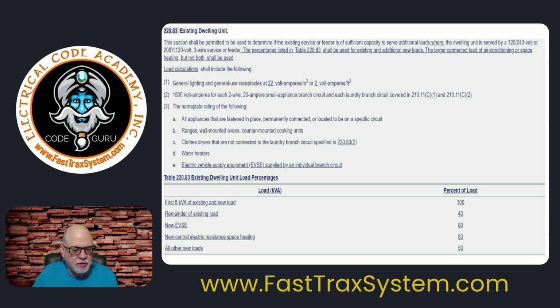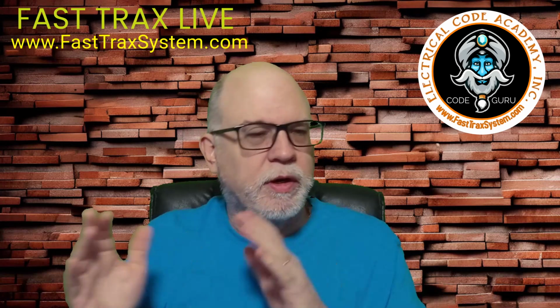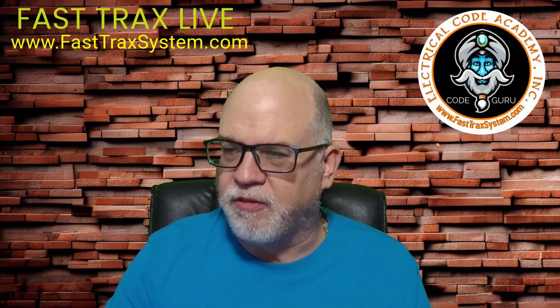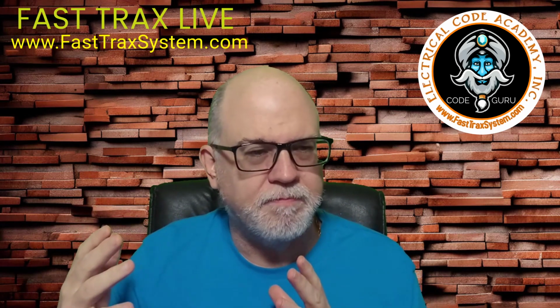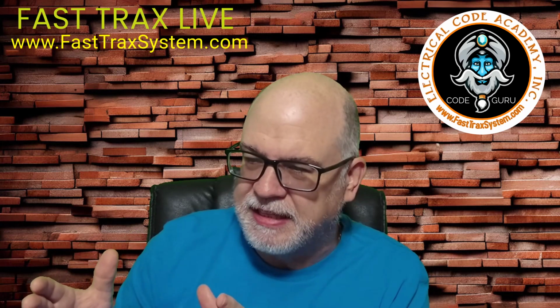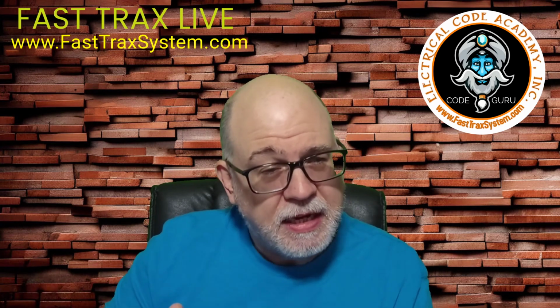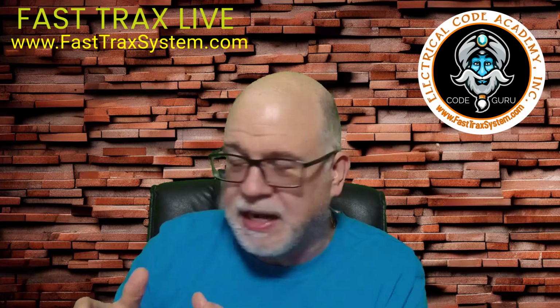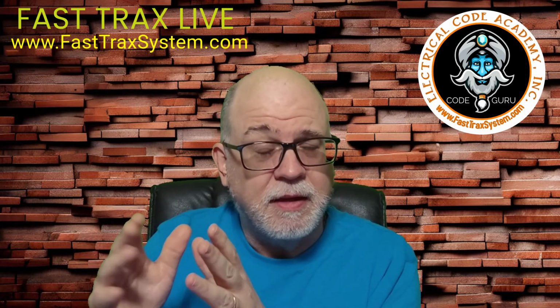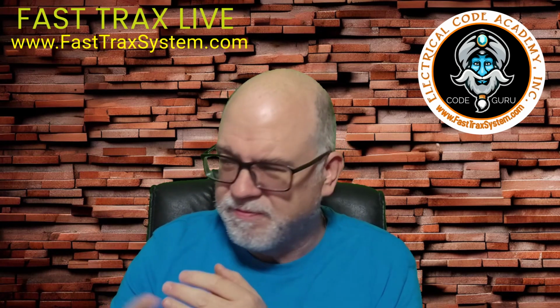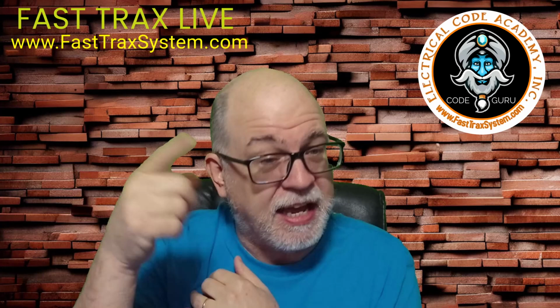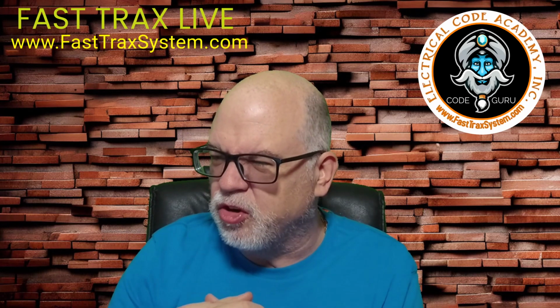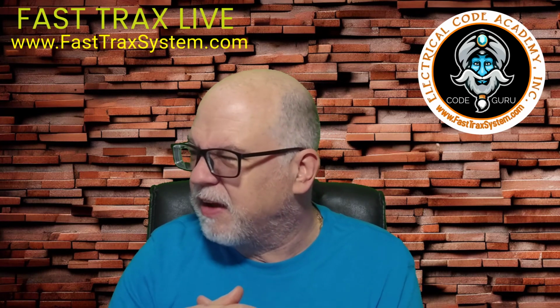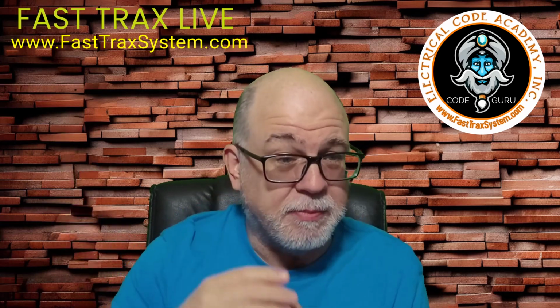So what we're doing here is simply giving you the ability to, in the 2026, we're going to say, okay, well, I have all of my existing loads. That's the first part. That's the part that I'm going to apply to the first 8,000 at 100%, and then the remainder over that at 40%, that's existing. And then if I've got any new EVSE, I'm going to take it at 80% and add it to that number. If I've got any new central electric space heating, I'm going to take that at 80% and add it to my total.